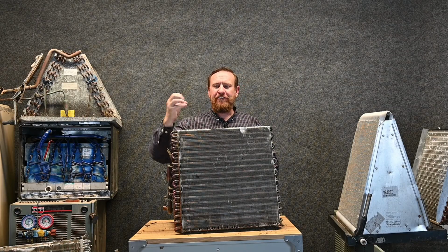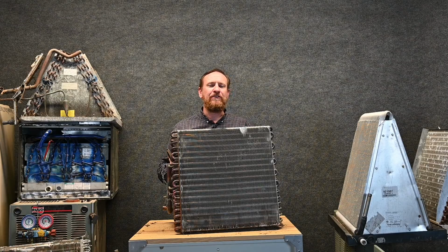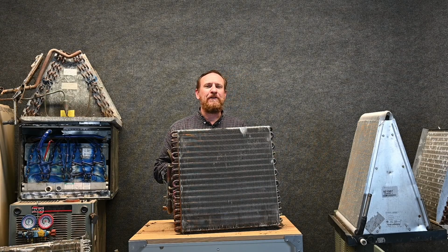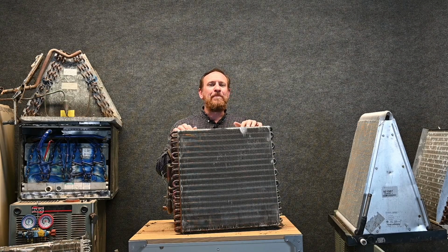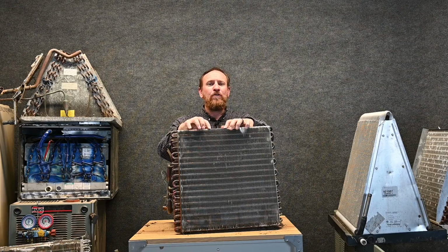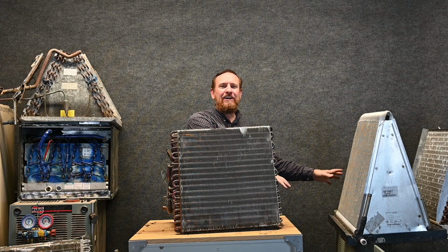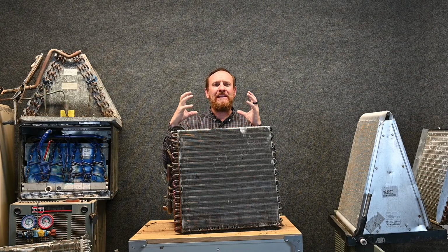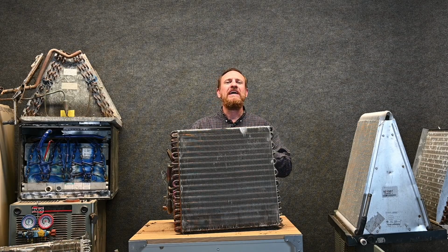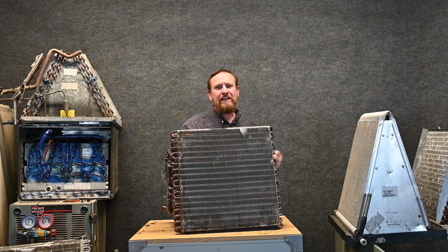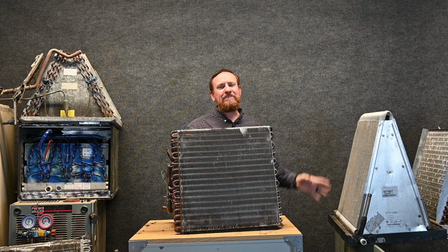That copper is now free floating inside of a refrigeration cycle. That copper then ends up at the compressor and it starts sticking to the hottest part of the compressor. So having an improper vacuum causes the acid to eat away the copper on the evaporator coil, and it causes copper plating on the compressor. So the compressor has these moving parts and the copper is building up, making the tolerances closer and closer and closer, and it starts wearing and pulling down on the compressor. Imagine somebody's running and a bunch of people are dragging them down. That's what's happening to your compressor.